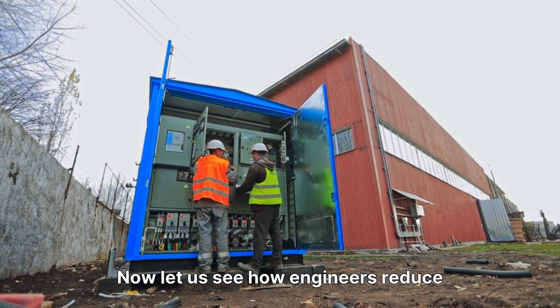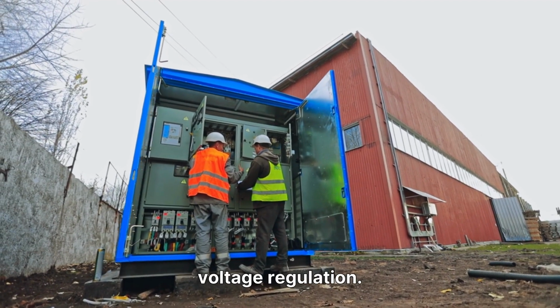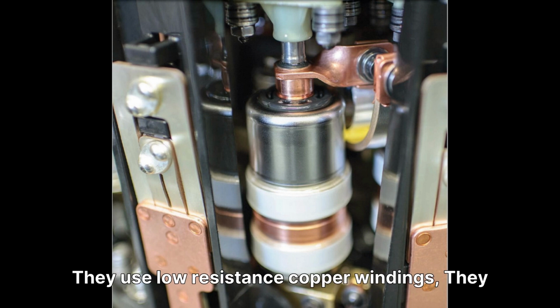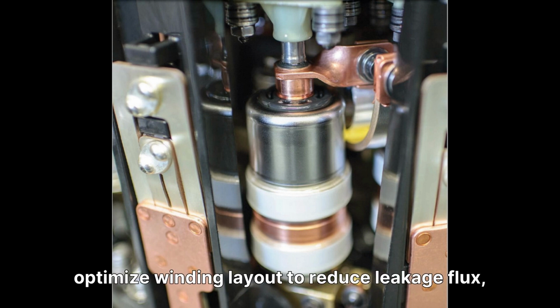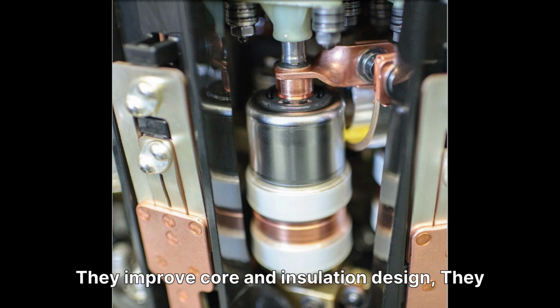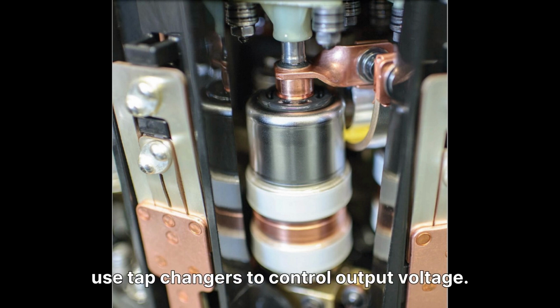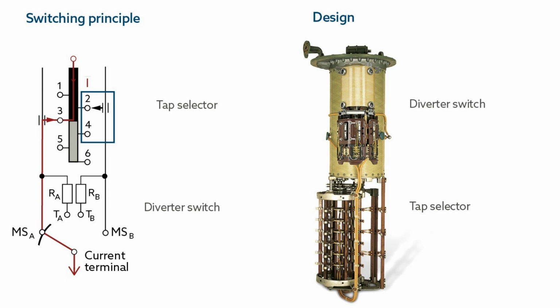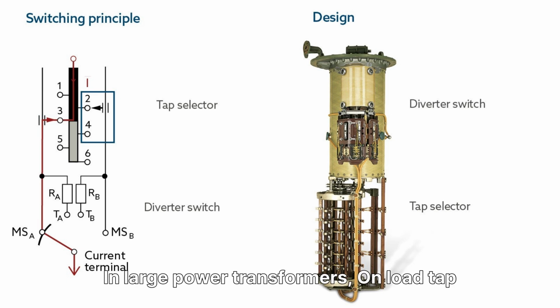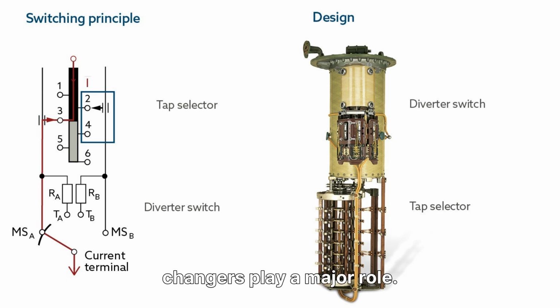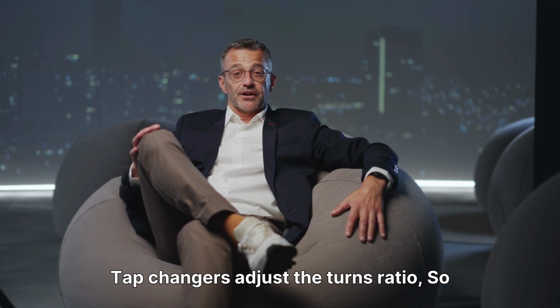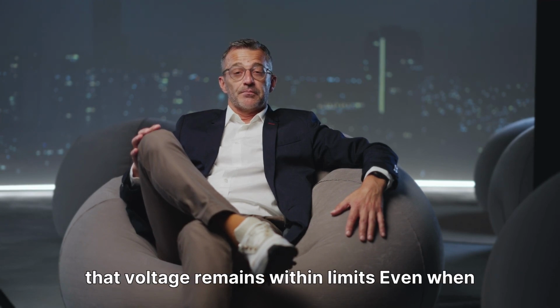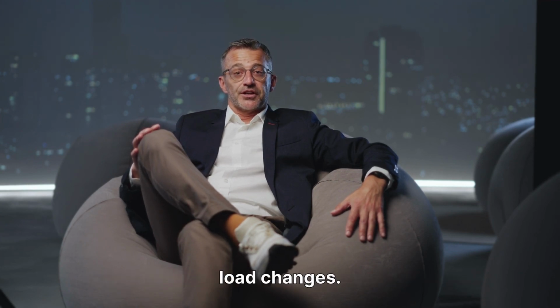Now let us see how engineers reduce voltage regulation. They use low-resistance copper windings. They optimize winding layout to reduce leakage flux. They improve core and insulation design. They use tap changers to control output voltage. In large power transformers, on-load tap changers play a major role. Tap changers adjust the turns ratio so that voltage remains within limits even when load changes.